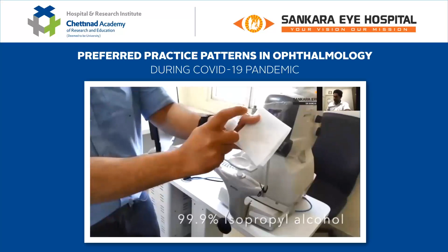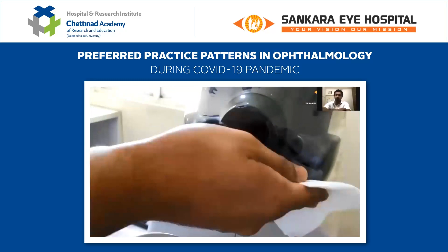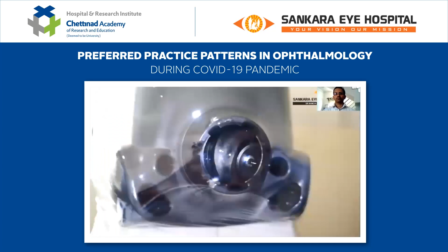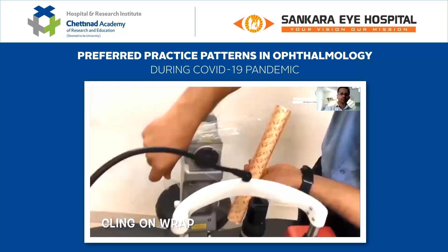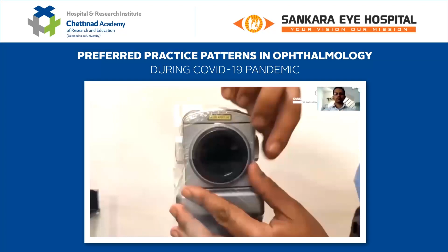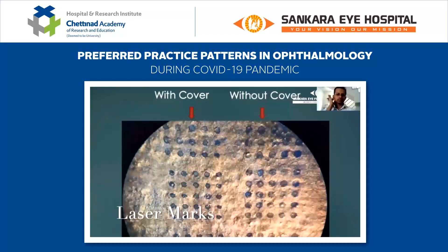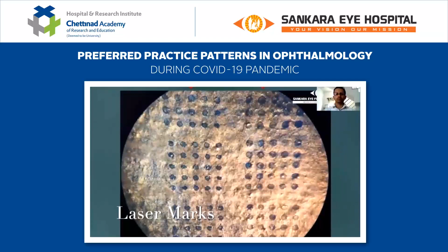For cleaning, isopropyl alcohol can be used. Take a clean tissue paper, spray isopropyl alcohol on it, and clean all around, especially the area covering the lens and the sensors. We can see that the cover is absolutely clear with no contamination or fogging. In a similar way, you can use a cling wrap to cover your Pascal laser delivery systems. Just make sure there are no bubbles or folds in the front surface. On comparing the laser marks with and without the cling wrap, we found that the ones obtained after putting the cling wrap were slightly smaller in size, but we did not find any significant difference in the clinical scenario.